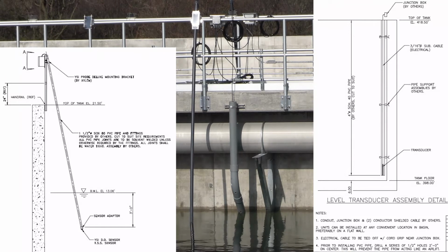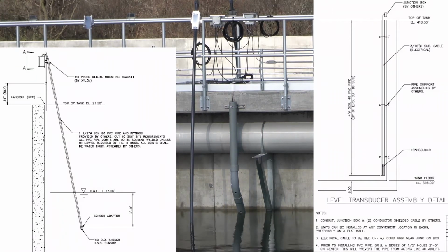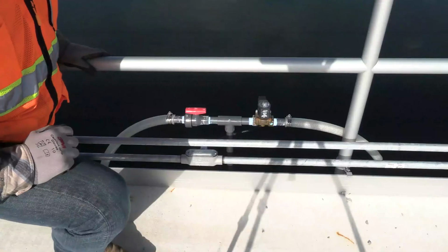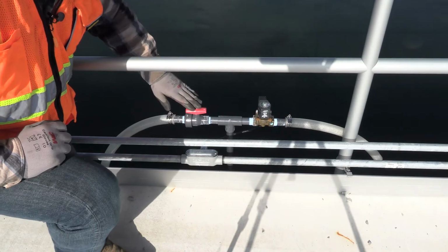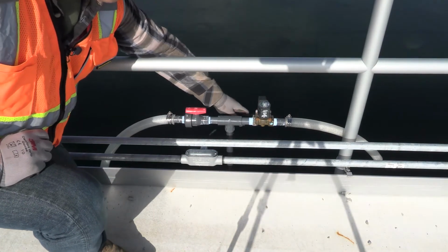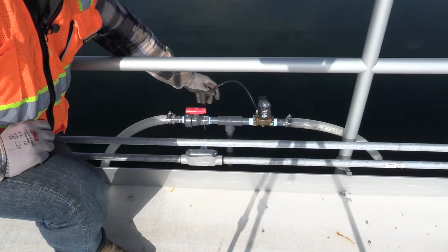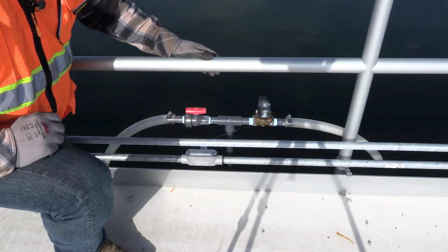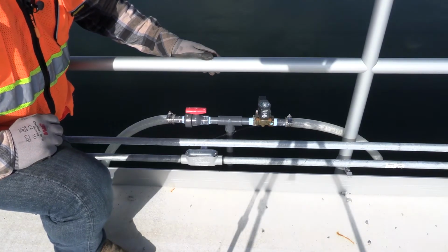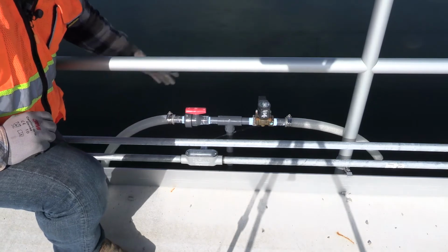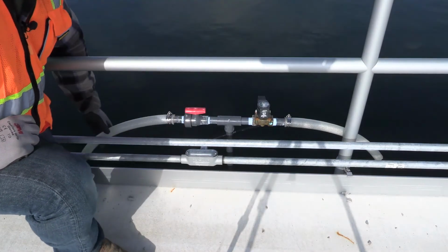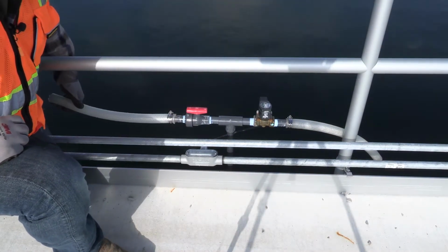But more importantly, if you look closely, you will see a 4-inch PVC stilling well. This is for the level transducer. It has 1/2-inch holes drilled every 24 inches and must be installed before our visit. Here we have automatic and manual purge valves. We will need a picture to confirm the wiring of this automatic purge valve. In colder environments, it is always good practice to have the purge go back into the basin and not on the deck. Here you can see they use some flexible hose to do this.